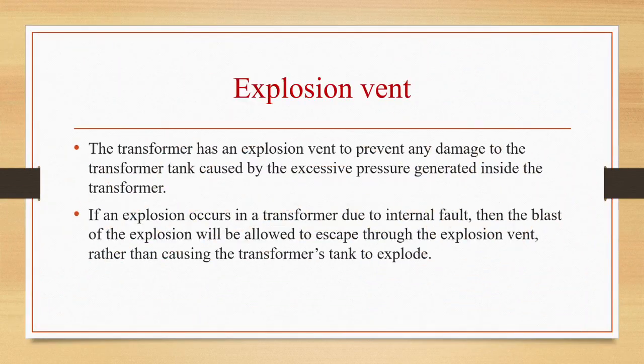Explosion vent. Transformer has an explosion vent to prevent any damage to the transformer tank caused by the excessive pressure generated inside the transformer. If an explosion occurs in a transformer due to internal fault, then the blast of the explosion will be allowed to escape through the explosion vent rather than causing the transformer's tank to explode.